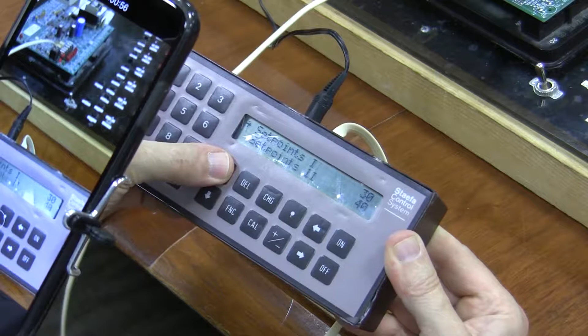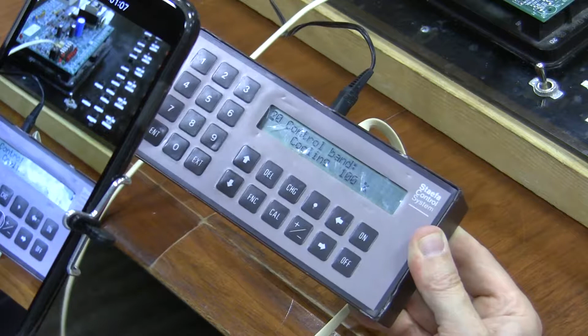Application status, and we're going to hit enter, and it says control band. Sure enough, cooling 100%. What does that mean it should have done, if I scroll down here? It probably changed our flow set point. Override time, primary air volume control is now at 300 feet per minute, which, again, if I actually look at that input, and I go to parameter number 3, I'm basically at set point now. Okay? So that's some stuff, you know. My intent here is to just show you how to use the service tool. You'll have to also learn some more about the function of the controller, which would be a different class.